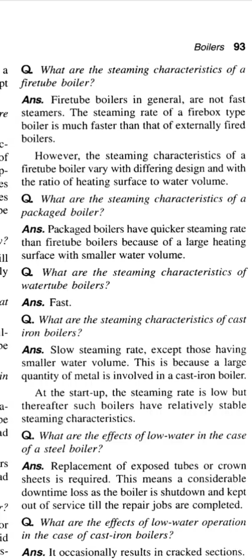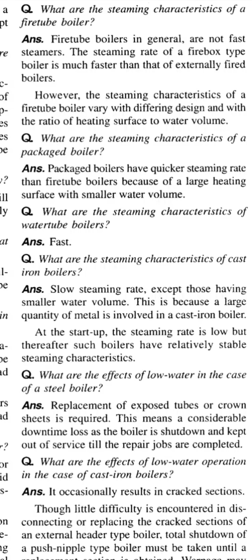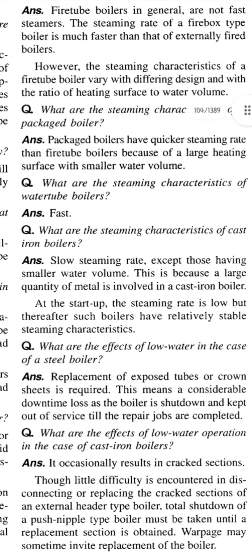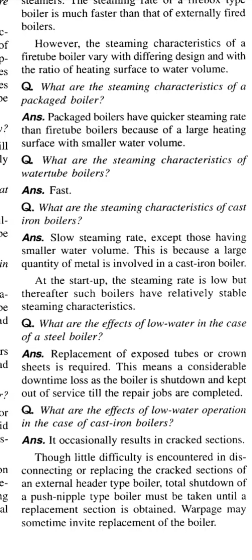Question: what are the steaming characteristics of a packaged boiler? Packaged boilers have a quicker steaming rate than fire tube boilers because of large heating surface with smaller water volume. What are the steaming characteristics of water tube boilers? It is fast. Question: what are the steaming characteristics of cast iron boilers? Slow steaming rate, except those having smaller water volume. This is because of the large quantity of metal involved in a cast iron boiler. At startup, the steaming rate is low, but thereafter such boilers have relatively stable steaming characteristics.